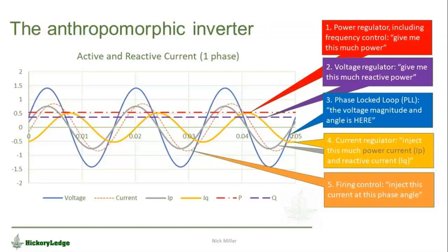There's another controller in parallel with that, particularly in North American applications, doing voltage regulation. It measures voltage error, does lots of things most of you are familiar with, and issues an instruction that says give me this much reactive power - that's the purple line. So those things look steady state, and you're used to seeing them in your stability program.